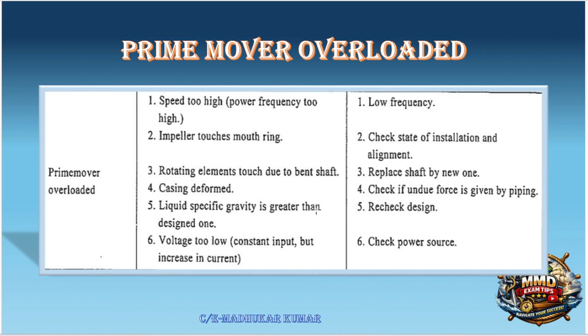Liquid specific gravity is greater than the designed one. Okay, so generally the pump is designed to work for a certain viscosity. If it is highly viscous, then big problem. So we have to increase the temperature and do whatever is possible. Otherwise, we have to use another pump, which is specifically designed to discharge the high specific gravity liquid. Voltage too low, constant input and increased current. Okay, so voltage too low, then again the electrical part, check the power source, why it is like that, and make sure that if it is due to any connection or any problem related to the main circuit breaker or something like that, then go with the electrical officer and make sure it is done correctly.